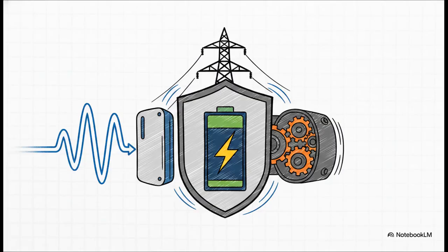Because of all this, today's grid operators are deploying a complete stability arsenal to make sure a 100% renewable grid won't just shake itself apart. We've got grid-forming inverters setting the pace, we have massive battery energy storage systems delivering that fast frequency response, and we also have these things called synchronous condensers, which are essentially just massive free-spinning motors that provide real, heavy physical inertia and short-circuit strength, but without actually generating any electricity themselves.